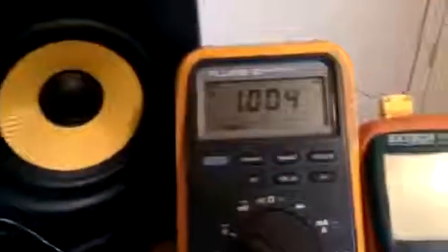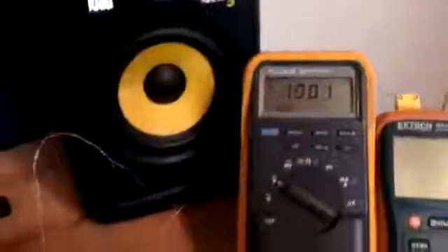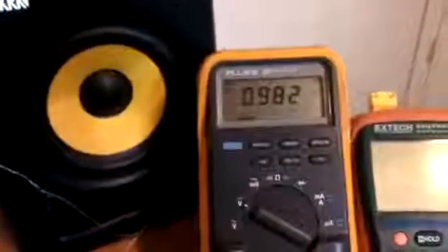Then if we raise the tube of the water up so that the depth is greater than the level of the transducer, the voltage changes, as you can see here. So what we need to do is we need to measure the voltages at multiple different points. So for example, we're going to measure about six inches high, then one foot, then so on, and measure the voltages at each of those points.